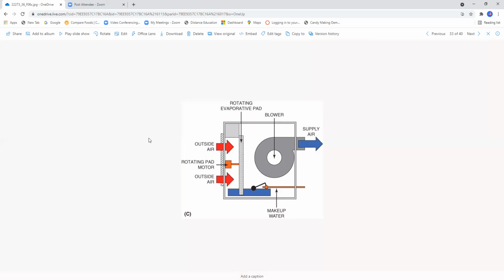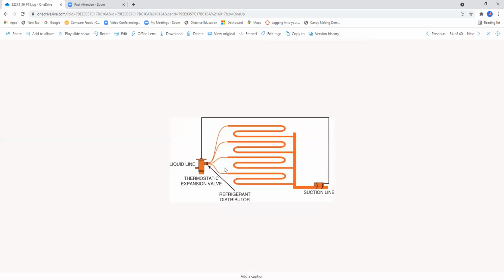The fan would draw the air through this wheel, which was like a stainless steel, copper brass construction. And the idea being, by that wheel picking up this moisture from the pan down below and rotating at slow speed, you would basically have a form of evaporative cooling, which worked out very well. The problem with this particular design was the water had to be dumped out frequently. Otherwise, it would become slimy, green, mold growth would take place. That was one of the pitfalls of this design. It worked though. Okay, here we have a thermostatic expansion valve.